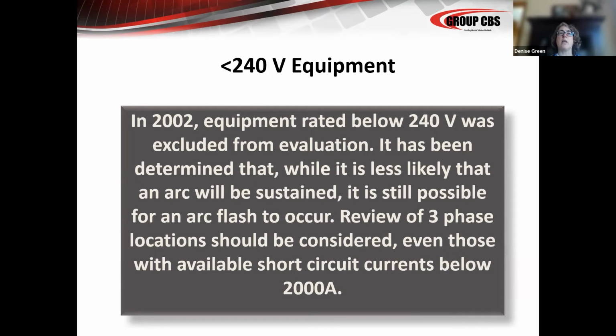Arc flashes, unless there's impending failure, happen when you're racking a breaker in, racking a breaker out, closing a breaker, and tripping a breaker. Those are normally the times that an arc flash incident happens, unless Frank left his crescent wrench in the gear 6 months ago and it finally vibrated over and fell across the back of the gear. That's a whole different topic.